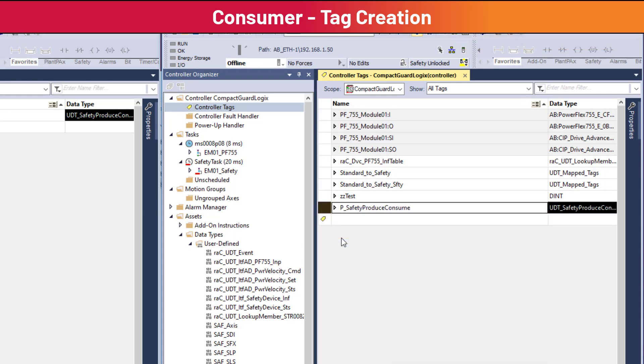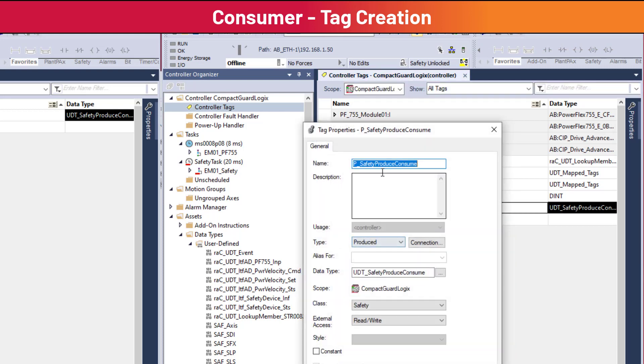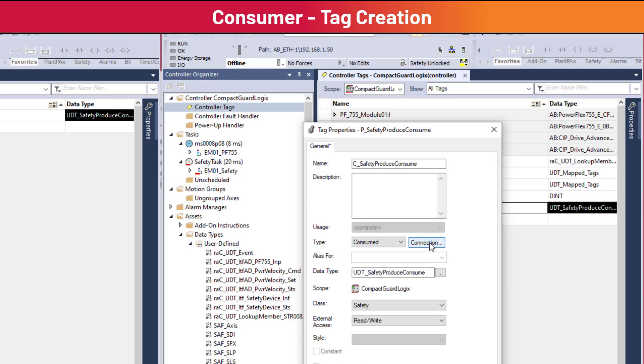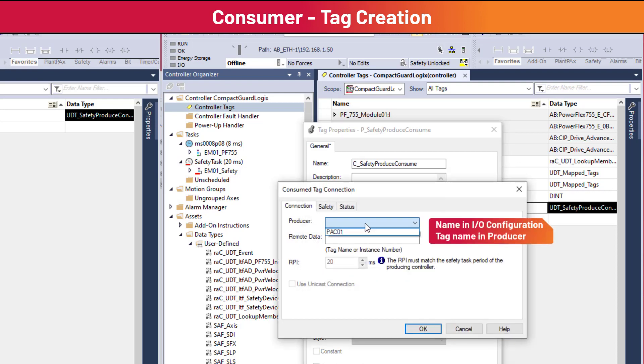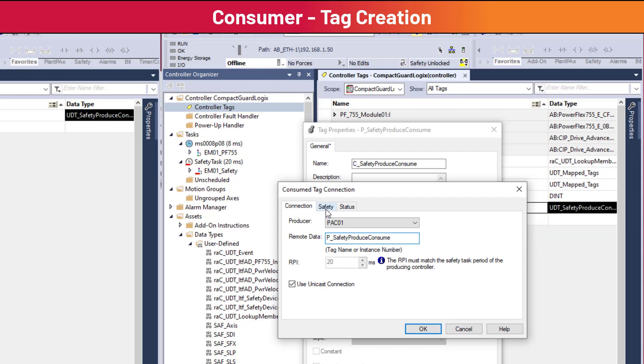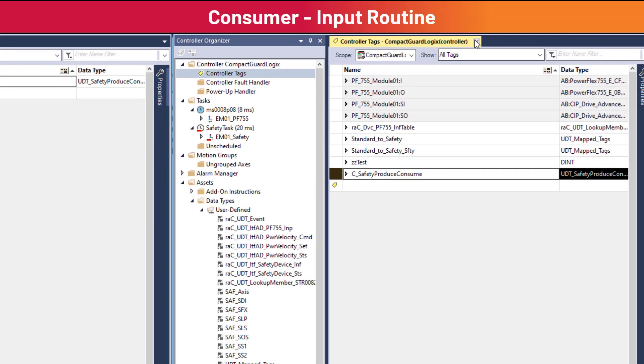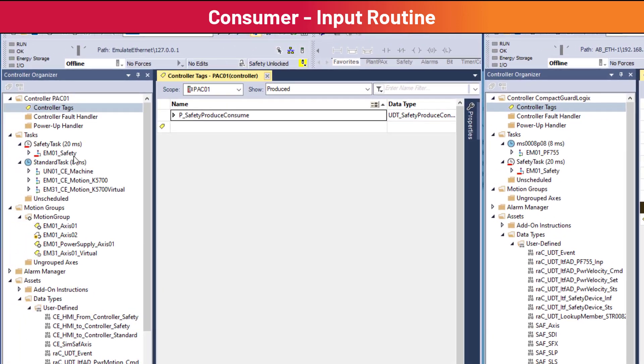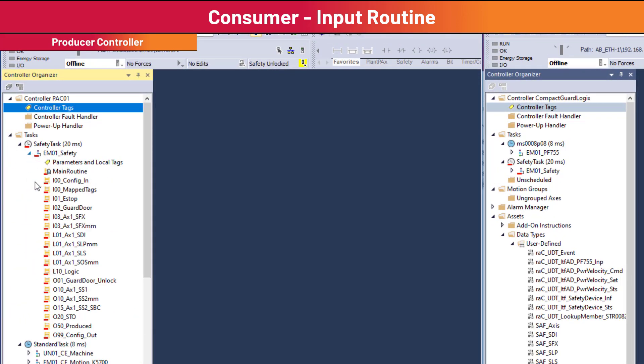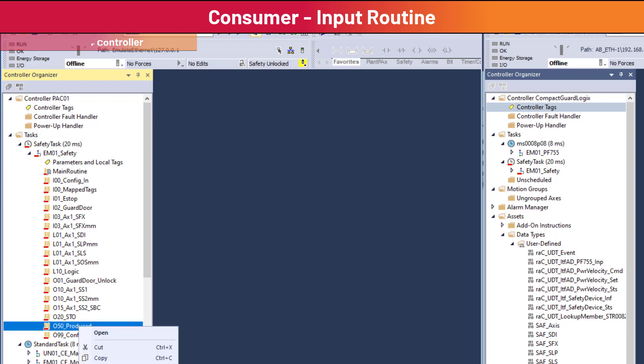Now edit the tag properties. Change the P to a C to indicate consumed, change the type to Consumed, and edit the tag connection to producer PAC01. Enter the remote data tag P_safety_produce_consume. The consuming connection RPI must match the safety task of the producer — change the RPI in the Safety tab if necessary. A programming best practice is to create an input routine for safety consumed data. The routine O50_produced is copied from the producer.